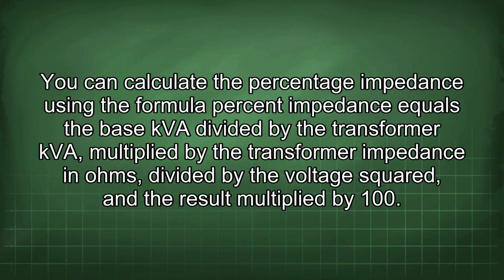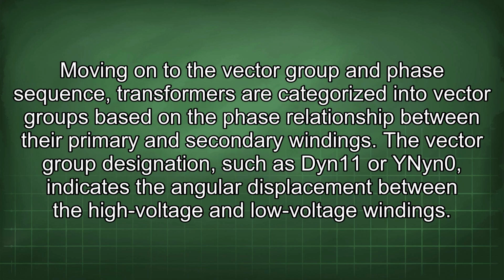You can calculate the percentage impedance using the formula: percent impedance equals the base kVA divided by the transformer kVA, multiplied by the transformer impedance in ohms, divided by the voltage squared, and the result multiplied by 100. Moving on to the vector group and phase sequence, transformers are categorized into vector groups based on the phase relationship between their primary and secondary windings.